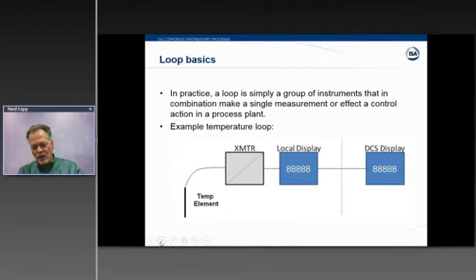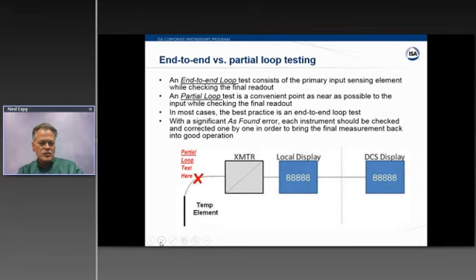So I've coined the term: an end-to-end test would be best practice. You would want to exercise the probe and compare your traceable test on the probe to the DCS display. Sometimes that's not practical. It may be difficult to pull the probe out of service where you can drop it into a dry block or a bath. So you may have to make a slight compromise and break into the loop.